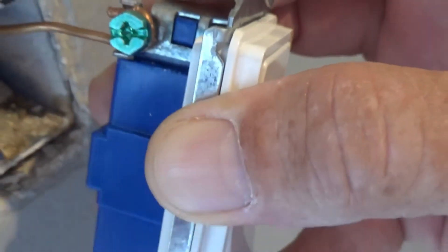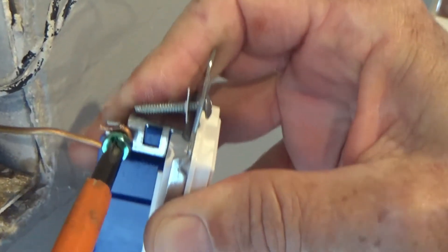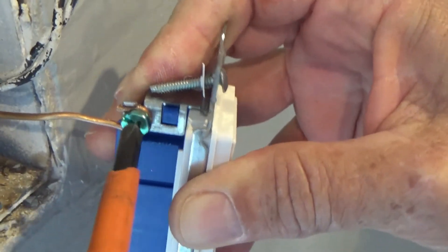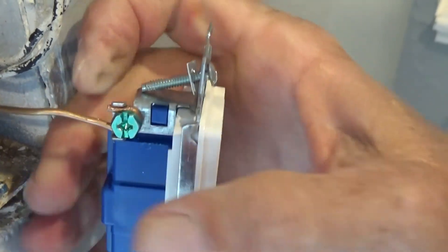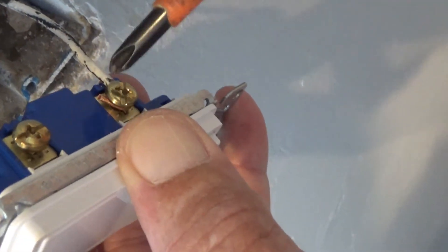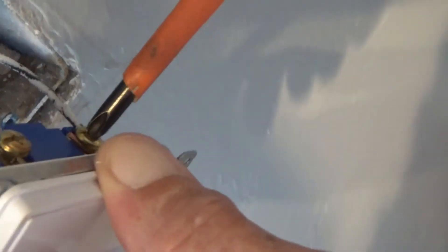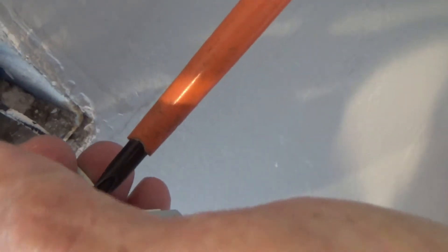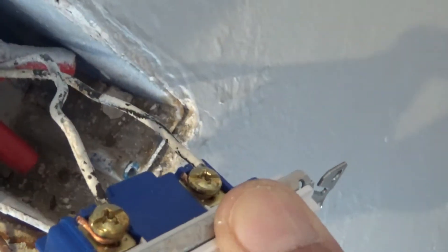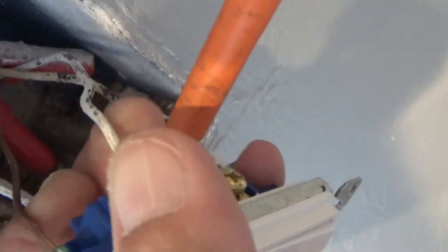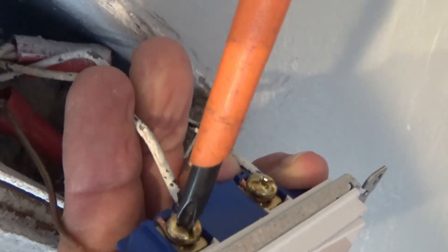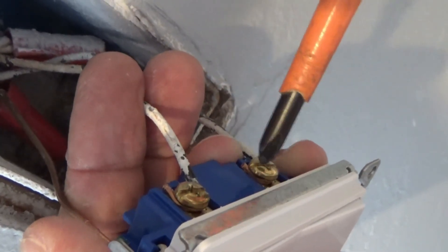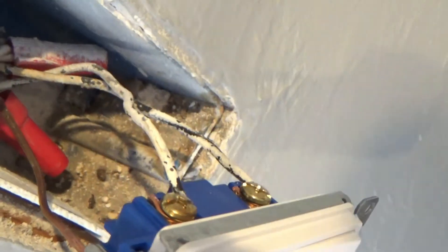On the top, we try to always do power out on the top of the switch, power in on the bottom of the switch. So he's attaching the power out, or the switch leg that goes up to the light fixture. Now he's attaching the power in, or the common. Always give it the extra tighten down because you don't want things to come loose.